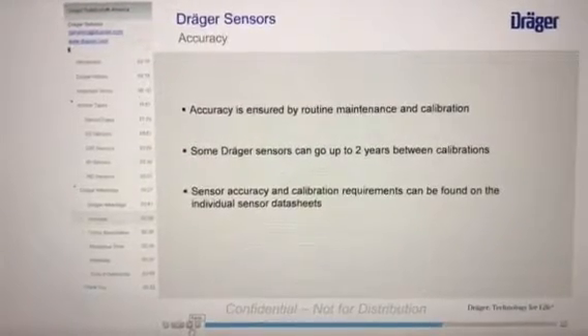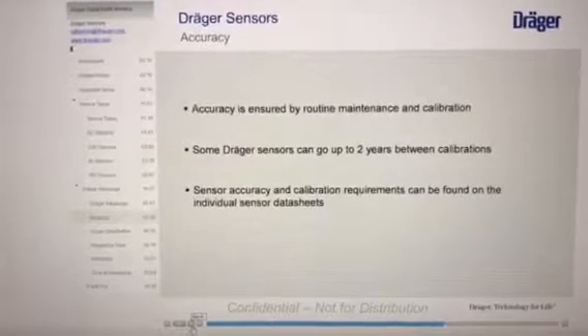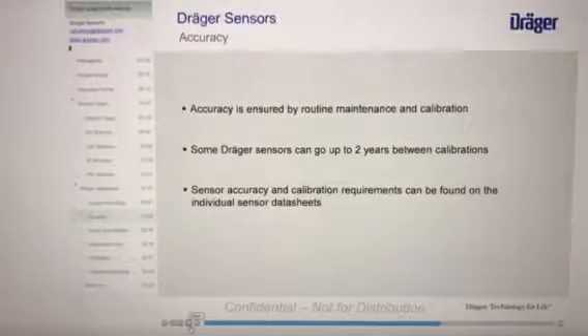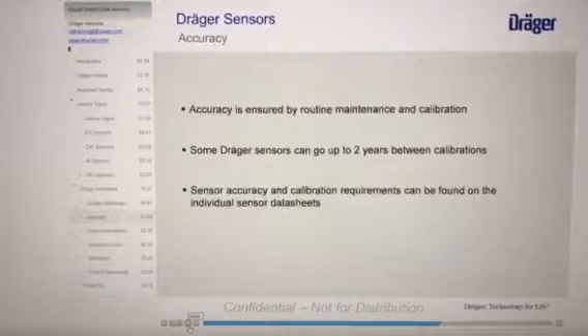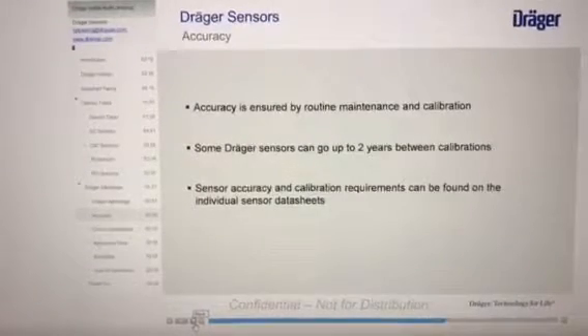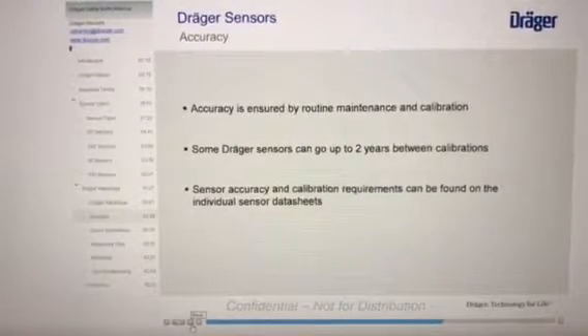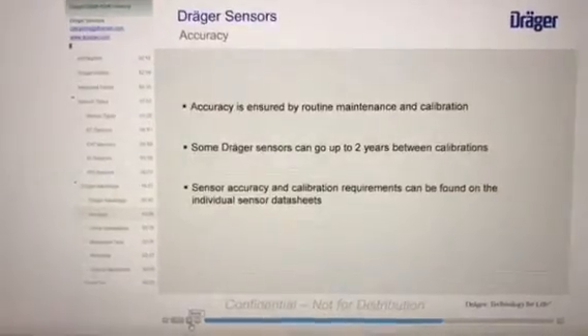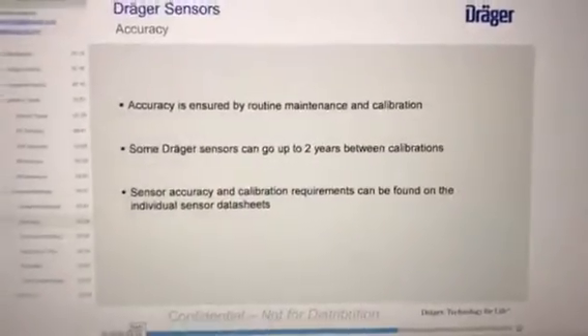The Draeger advantage is apparent when you compare this to competitive sensors for the same gas. For example, one competitive sensor has measurement accuracies of plus or minus 15% and can require calibration as often as every 3 months. For more information, the sensor accuracy and calibration requirements can be found on the individual sensor datasheet.